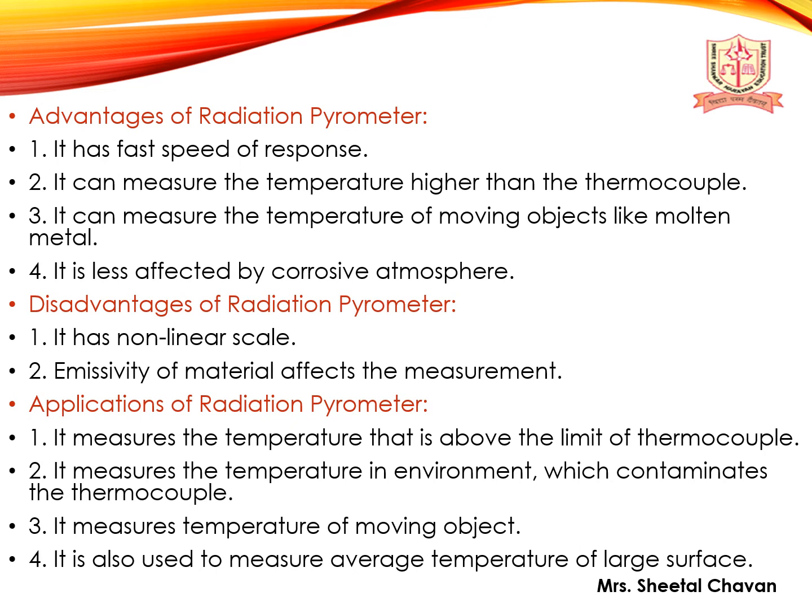Advantages of radiation pyrometer. It has a fast speed of response. It can measure temperatures higher than a thermocouple. It can measure the temperature of a moving object like molten metal. It is less affected by corrosive atmosphere. Disadvantages of radiation pyrometer. It has a non-linear scale. Emissivity of the material affects the measurement.